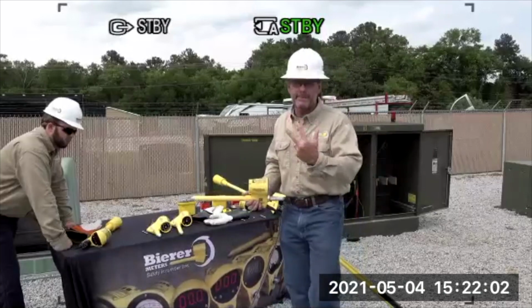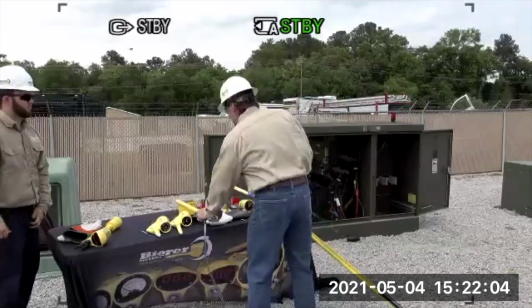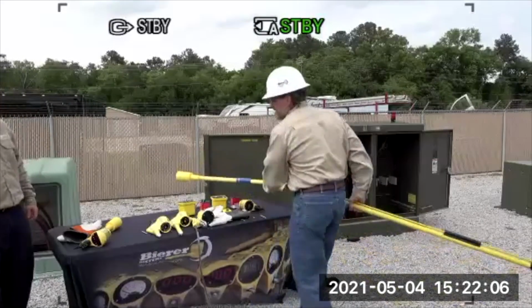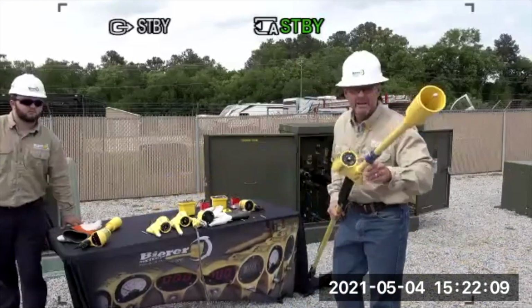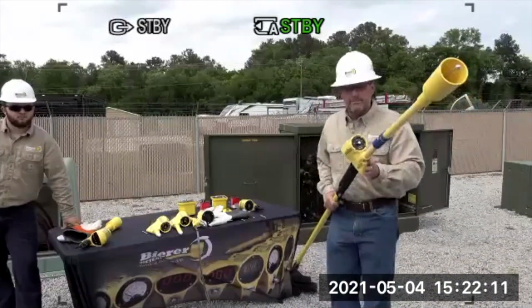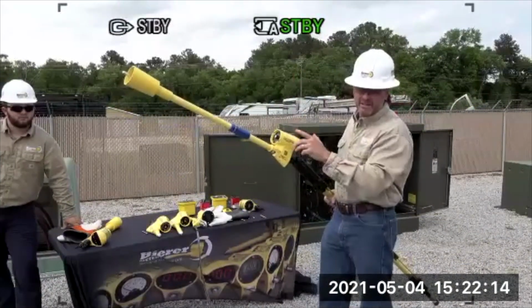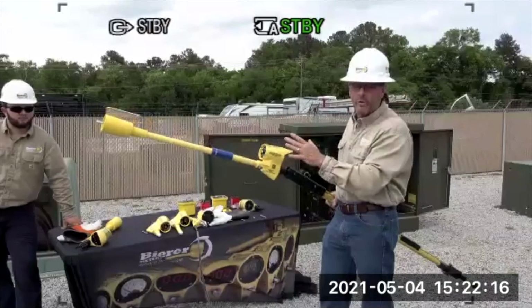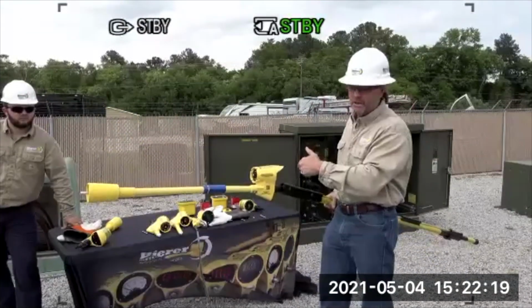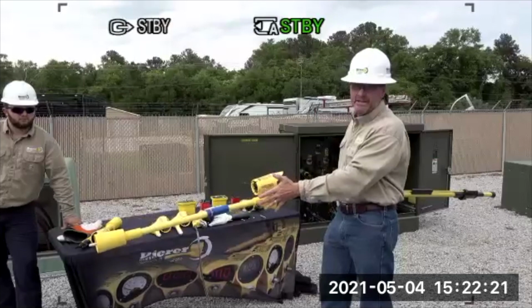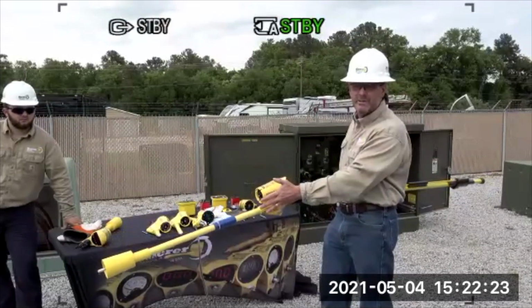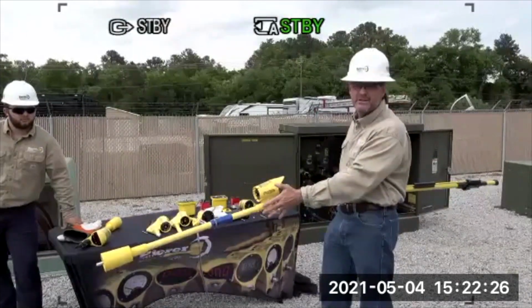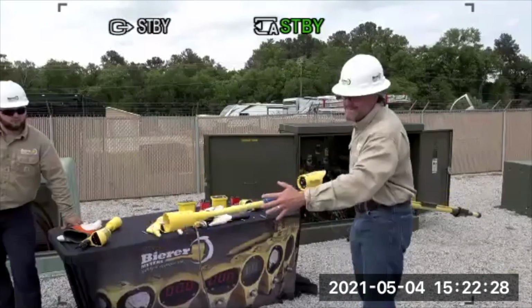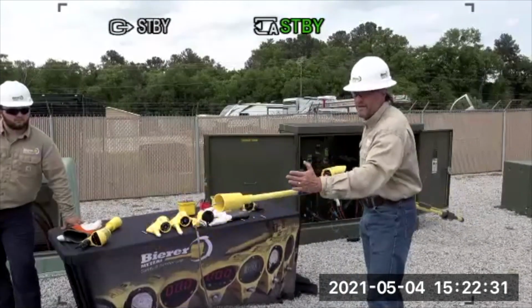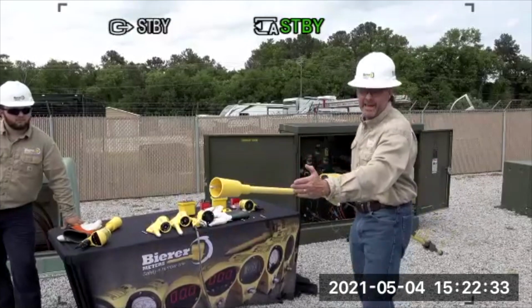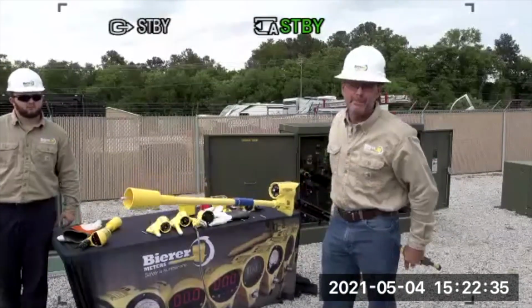So you want to visually inspect, and you're going to use a zero ohm extension right here. Before we touch that hot conductor in the substation, or before we go into that tight vault, we're going to visually inspect and see that the meter head's too close to that potential hot phase or too close to that potential ground. So we put a zero ohm extension on—here's before and here's after—and that prevents that arc flash from happening.